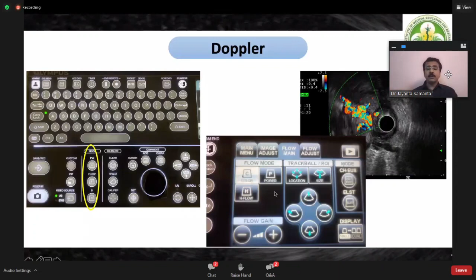Another important aspect of EUS imaging is tissue harmonics. What is tissue harmonic? Basically, a lot of waves are generated by the transducer, hit the tissues and come back. The fundamental echo signals are those generated by the transducer. And then there are certain echo signals which are generated particularly by the tissues. Those are known as the harmonic echo signals. So once we switch on the tissue harmonic, the signals the transducer is receiving get filtered, and only the harmonic echo signals generated by the tissues get captured by the transducer. This option is available on the keyboard.